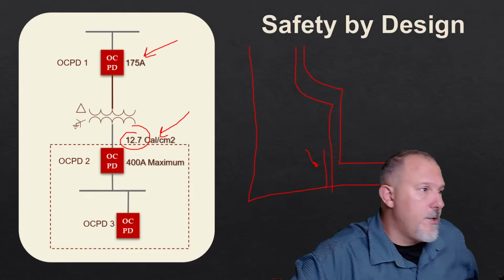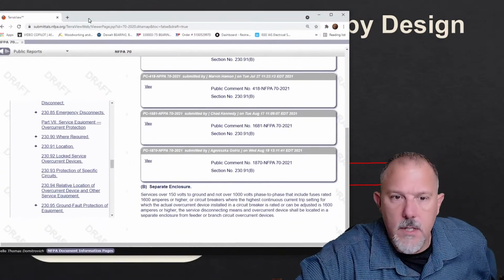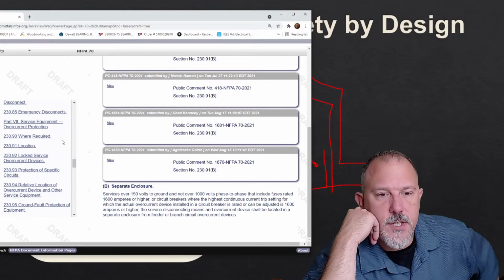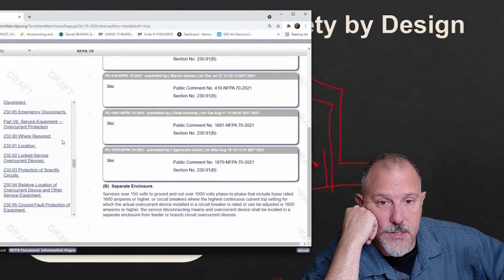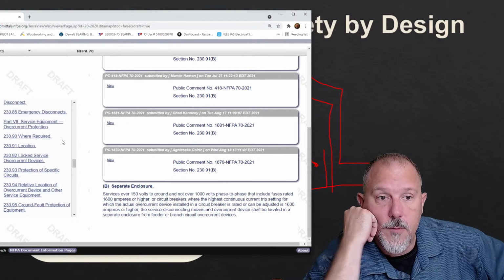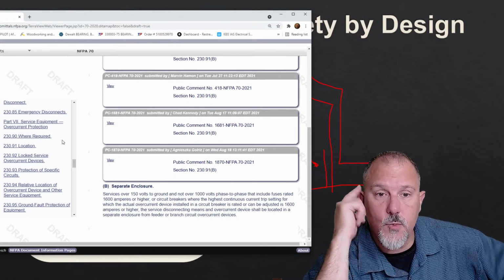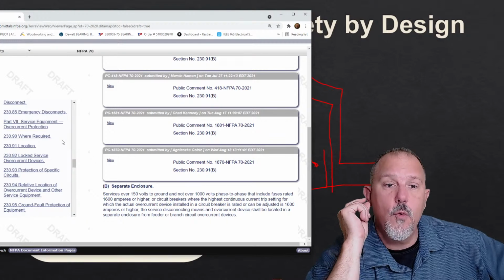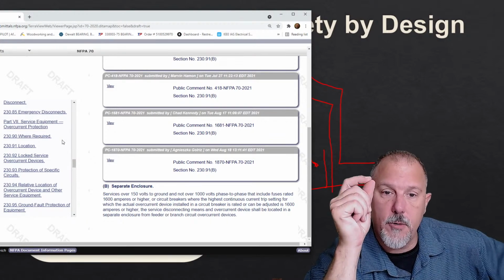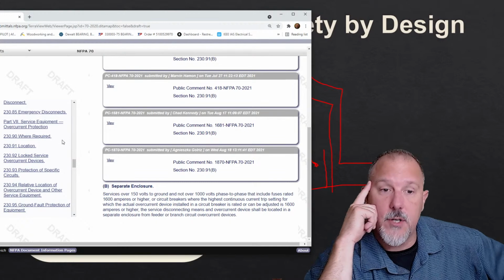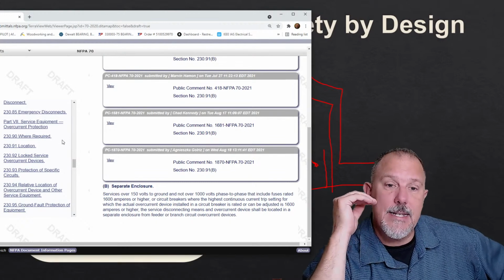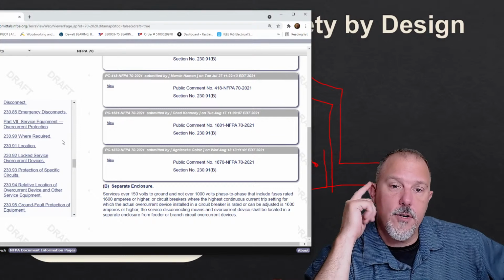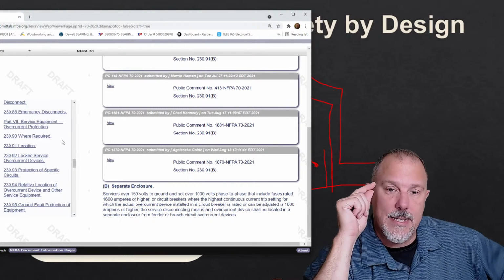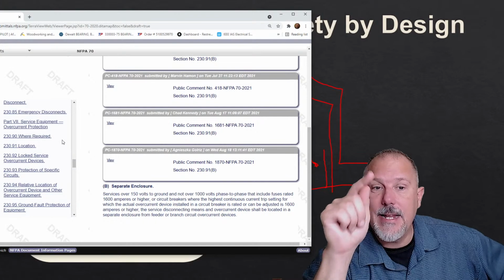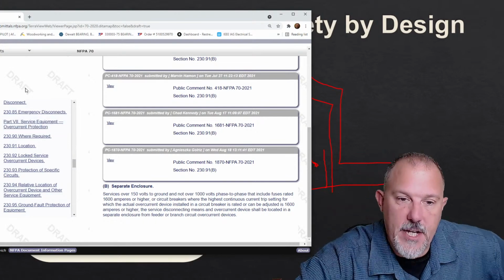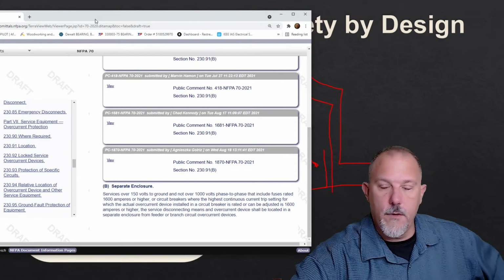Separate enclosures. So here's what the language said, and this is what he's talking about. Services over 150 volts to ground and not over 1,000 volts phase to phase that include fuses rated 1,600 amps or higher, or circuit breakers where the highest continuous current trip setting for which the actual overcurrent device installed in a circuit breaker is rated or can be adjusted is 1,600 amps or higher. The service disconnecting means and overcurrent device shall be selected or shall be located in a separate enclosure from the feeder or branch circuit overcurrent devices.